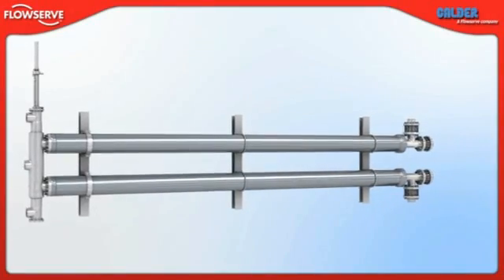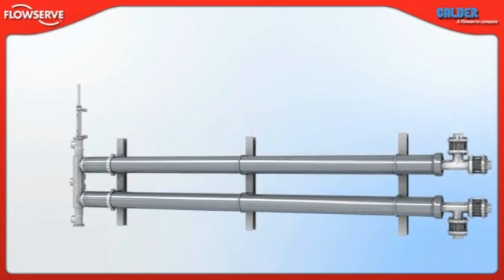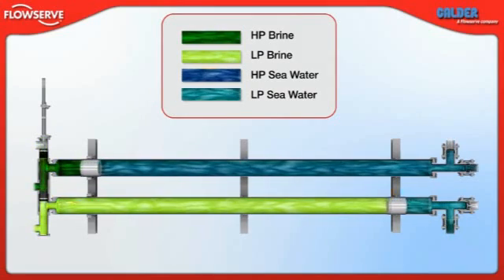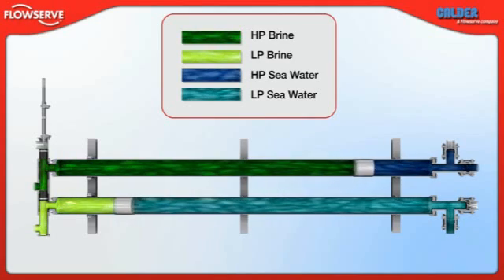With energy recovery systems, maximizing efficiency is critical. Able to recover up to 98% of the energy in the brine stream, the DWEER is an extremely efficient machine. By their nature, isobaric energy recovery devices are highly efficient, but like all machines, they are subject to system losses that degrade performance. For isobaric devices, those system losses are mixing, leakage, overflush and differential head.